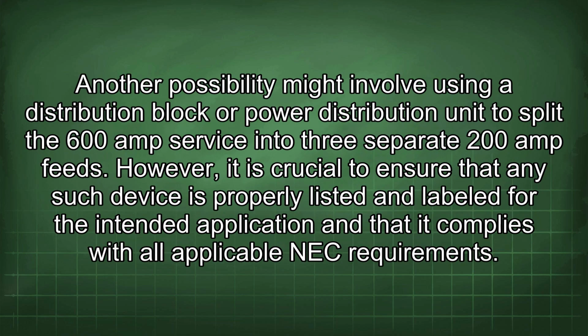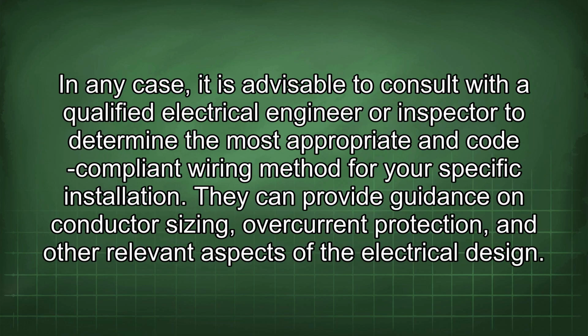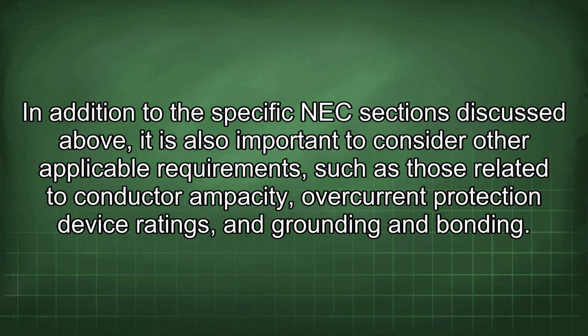Another possibility might involve using a distribution block or power distribution unit to split the 600 amp service into 3 separate 200 amp feeds. However, it is crucial to ensure that any such device is properly listed and labeled for the intended application and that it complies with all applicable NEC requirements. In any case, it is advisable to consult with a qualified electrical engineer or inspector to determine the most appropriate and code-compliant wiring method for your specific installation. They can provide guidance on conductor sizing, overcurrent protection, and other relevant aspects of the electrical design. In addition to the specific NEC sections discussed above, it is also important to consider other applicable requirements such as those related to conductor ampacity, overcurrent protection device ratings, and grounding and bonding.